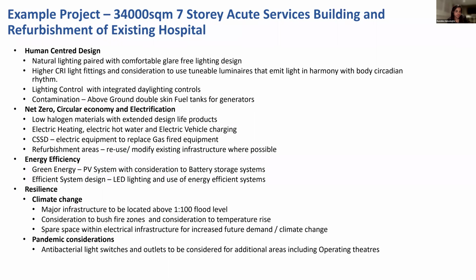And also we always consider climate change and resilience to climate changes. So if it is within a flood level, all major electrical infrastructure needs to be located above 1 in 100 flood levels. As per the Power Supply Authority standard requirements, all substations need to be installed above 1 in 100 flood levels. But in addition to that, we always try to put our major infrastructure, including the main switchboards, generators, etc., above this flood level as well, so that we can ensure the resilience of the services.